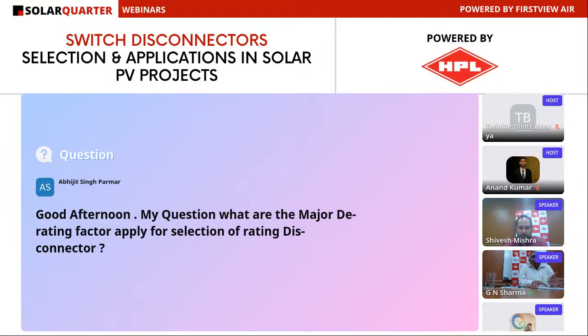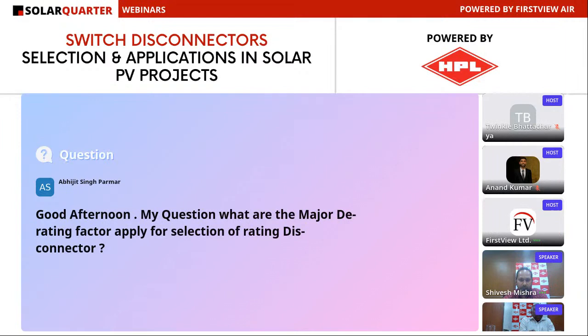At switchgear level, we keep an ample margin in these products. The allowed standard limit is very high: 70 degrees in a fresh switch, and 80 degrees in a switch that has had a lot of electrical life and faults. We try to certify the product with a temperature rise of less than 50 degrees or so, keeping a good margin of 20-30 degrees centigrade so that it works well in spite of all these conditions. This is our approach to handling it. If conditions are further worse, the right approach is to go for a higher version of switch.